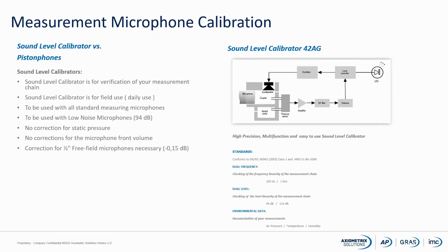We need to do a little correction when we are measuring half-inch free-field microphones, because with a calibrator we are doing a pressure measurement, a pressure calibration, and a free-field microphone is actually about 0.15 dB down at 1 kilohertz. So it's only at 1 kilohertz we have to do these corrections.